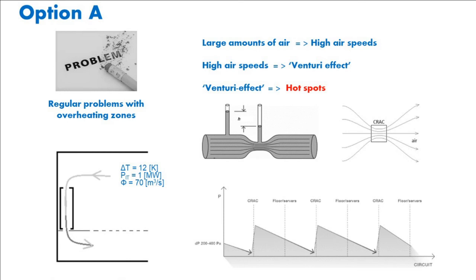For 1 megawatt of cooling, we need air delta T of 12 Kelvin and airflow of 70 cubic meters per second. When passing through a narrow section of the conditioner with high resistance to the heat exchanger, we obtain a considerable pressure drop, which leads to the appearance of a Venturi effect, causing overheating zones. Due to the need for high overpressure, we see a pressure drop along the air circulation loop of 200-400 Pascal, which also leads to high energy consumption by fans and their shorter life. For air-air systems, this figure is higher due to longer distances.